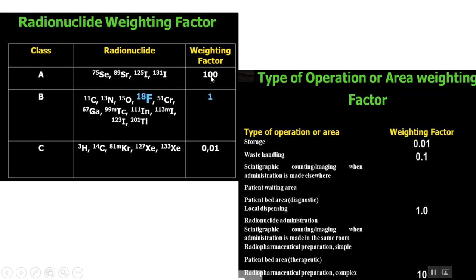Based on the type or area of operation, there are different weighting factor values. For storage with no active operations, the weighting factor is very low at 0.01. For simple administration areas, the weighting factor is 1, reflecting active work with radioactive material. You multiply the administered activity by these two weighting factors to classify the hazard of any nuclear medicine facility.